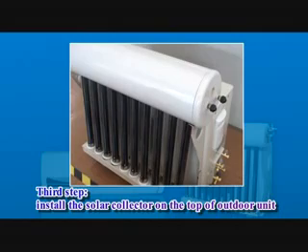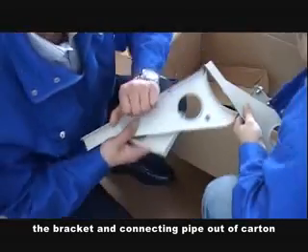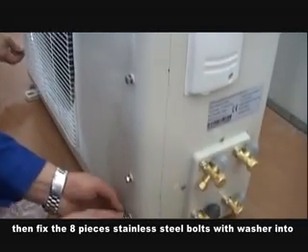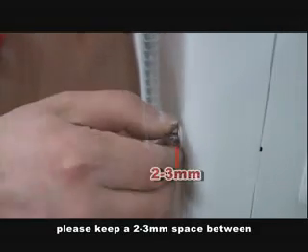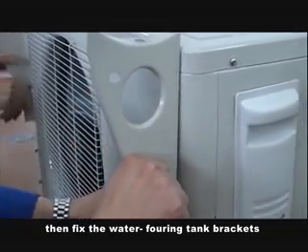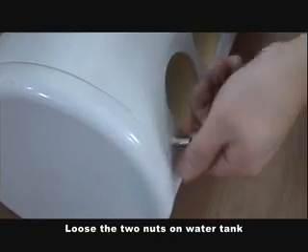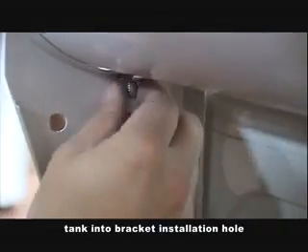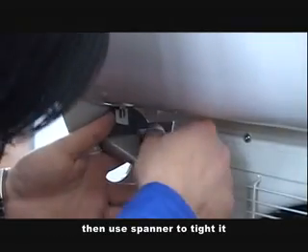Third step: install the solar collector on the top of the outdoor unit. Take the water tank, the bracket, and the connecting pipe out of the carton. Fix the eight pieces of stainless steel bolts with washers into the screwing holes of the front panel of the outdoor unit. Do not screw too tight — keep a 2–3 mm space between the front panel and outdoor unit. Then fix the water tank brackets on the front panel of the outdoor unit and tighten with wrench. Use the two nuts on the water tank, then put the water tank on the water tank bracket.